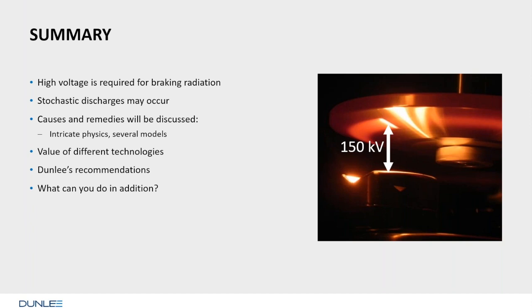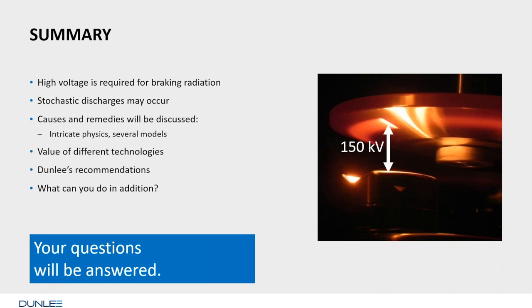an anode of an operating X-ray tube, a glass tube. Actually, we can look inside and see the focal spot. We see 150 kilovolts between cathode and anode, and it's just an inch away. So the electric field is pretty high. We will see where the causes are and remedies. It's a little bit intricate, as I said, and there are several models available. We will go through a few of them. We will discuss the value of different technologies, insulation technologies, glass versus ceramics, and so on. We will go a little bit through Dunlee's recommendations, and the question would be, what can you do in addition? And I hope that I will be able to answer your questions.